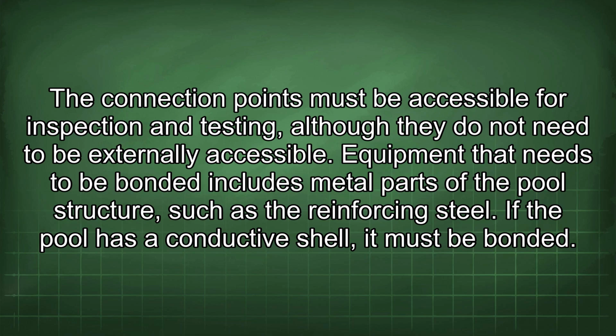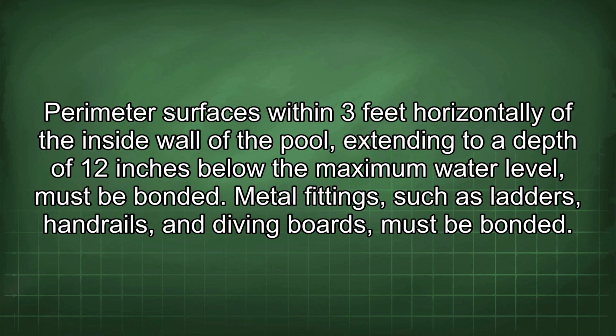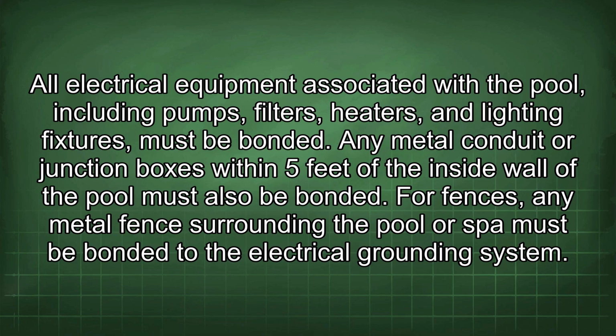Equipment that needs to be bonded includes metal parts of the pool structure, such as the reinforcing steel. If the pool has a conductive shell, it must be bonded. Perimeter surfaces within 3 feet horizontally of the inside wall of the pool, extending to a depth of 12 inches below the maximum water level, must be bonded. Metal fittings, such as ladders, handrails, and diving boards, must be bonded. All electrical equipment associated with the pool, including pumps, filters, heaters, and lighting fixtures, must be bonded. Any metal conduit or junction boxes within 5 feet of the inside wall of the pool must also be bonded.